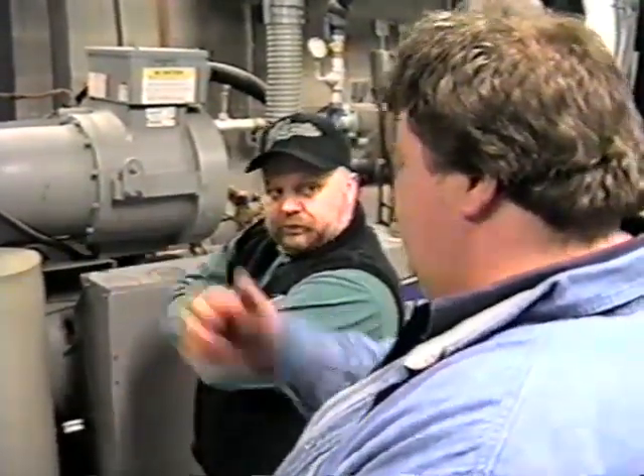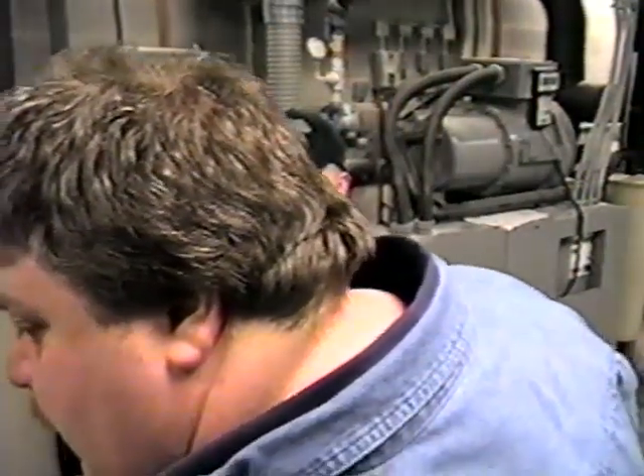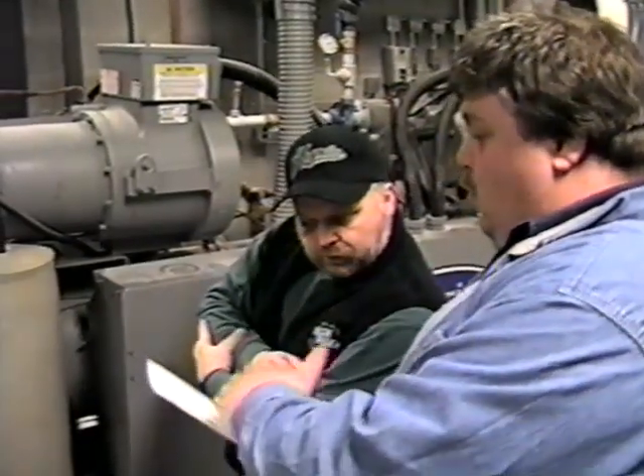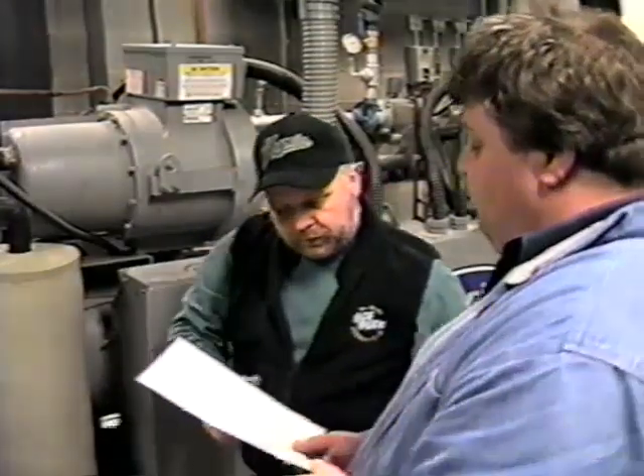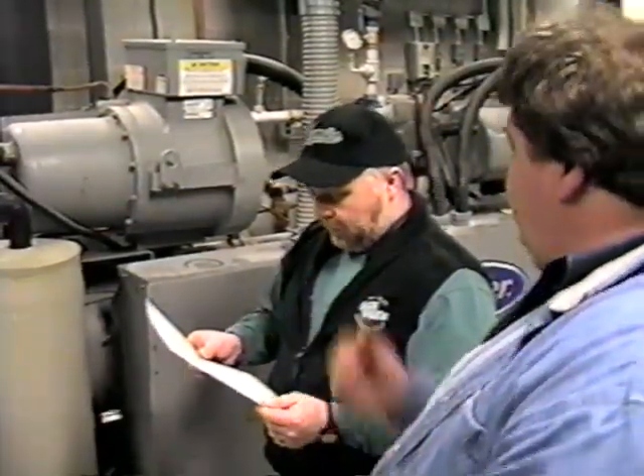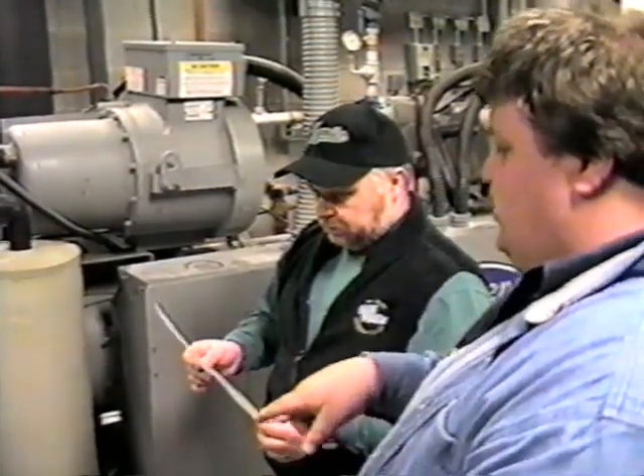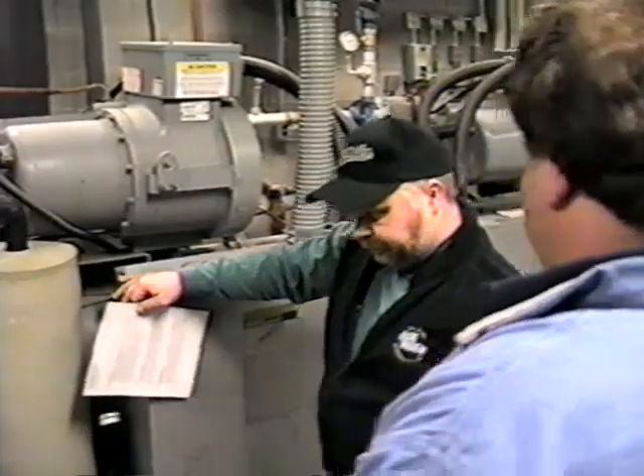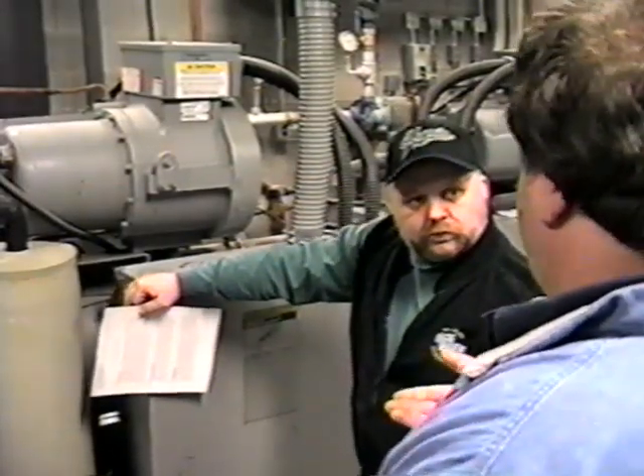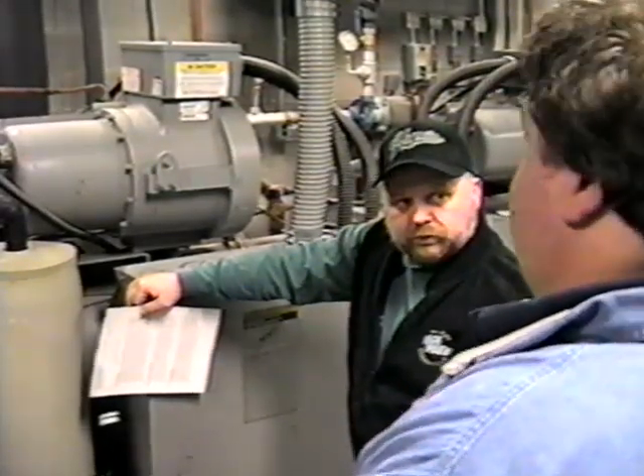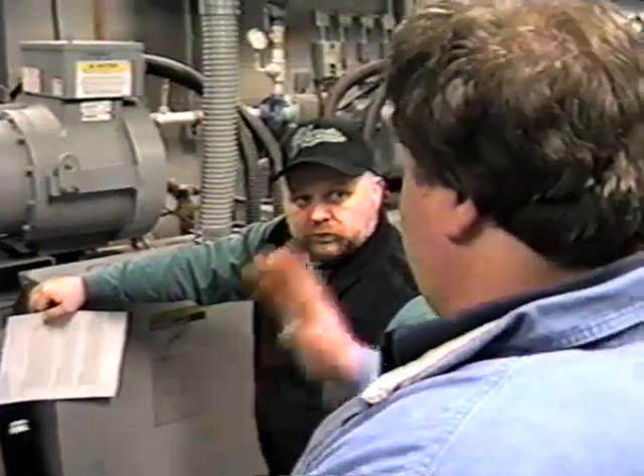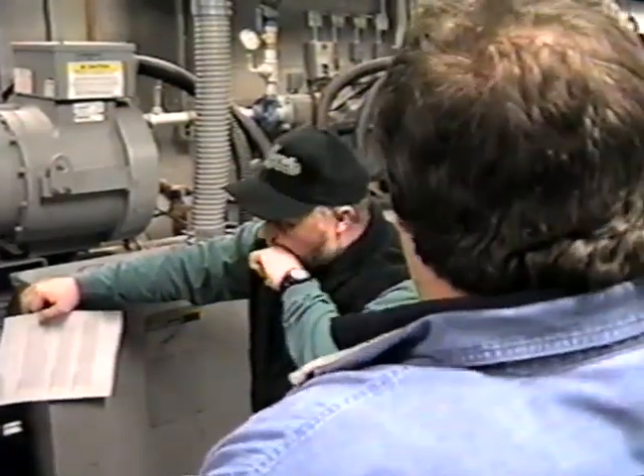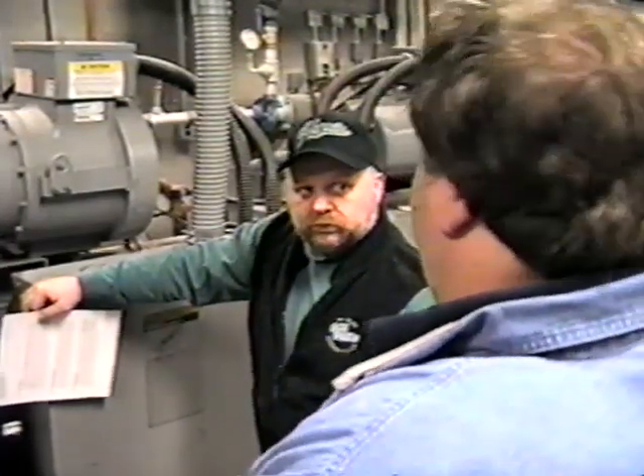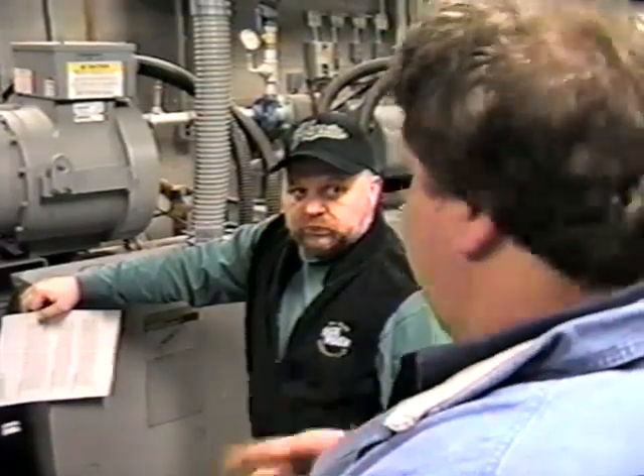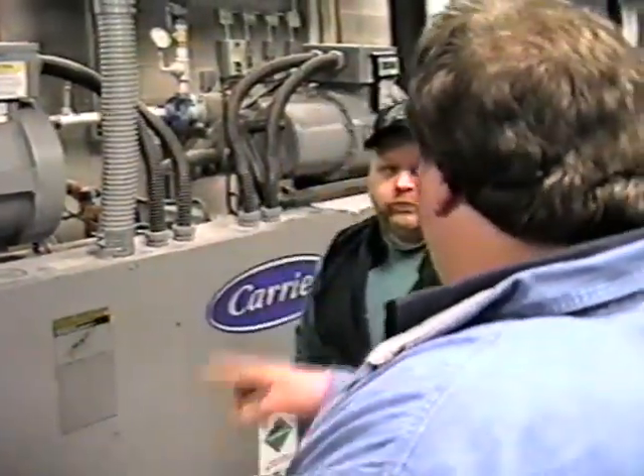Like I say, I'll give you a sequence of operation, and you should be able to go down through this. I wrote it in the format that you're going to see here, and it should make sense what should have happened next. Once it does its little time delay, it'll go to low speed, and the chiller will probably still be on, but within a minute it'll cycle down and shut right off. The only things that stay online are your condenser fan as the condenser water temperature ramps down, the bypass valve as it starts closing down, and your condenser water pump, which stays on for 10 minutes past whatever the chiller does, so that we make sure we don't have any freezing problems in the barrel.